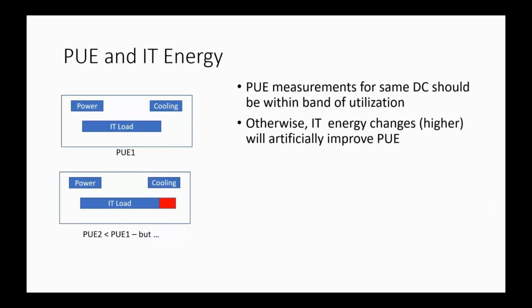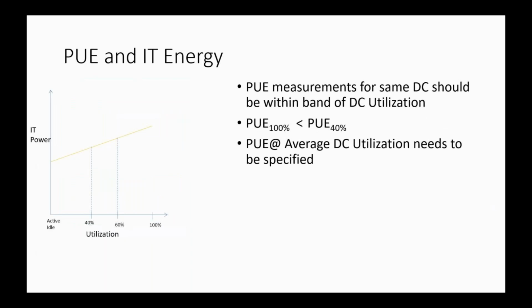Then I talked about the IT load. One of the games folks play is they know what time of the year or month they're calculating PUE, and at that point they can increase or decrease their IT load to get a favorable PUE. So at what IT load are you measuring is another subscript you need, because PUE calculated at 100% utilization is much different than PUE calculated at 40% utilization.